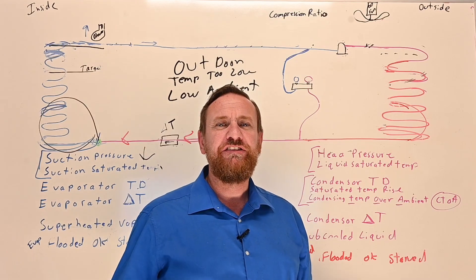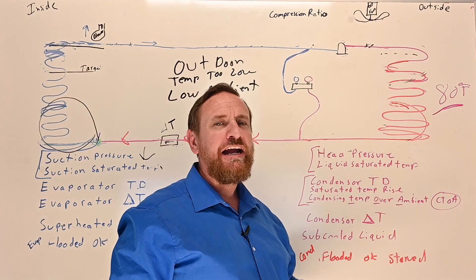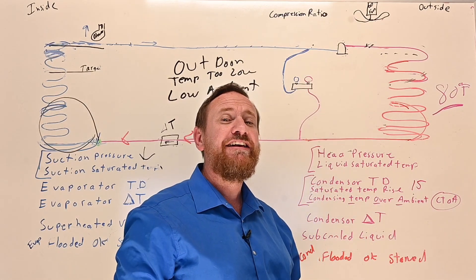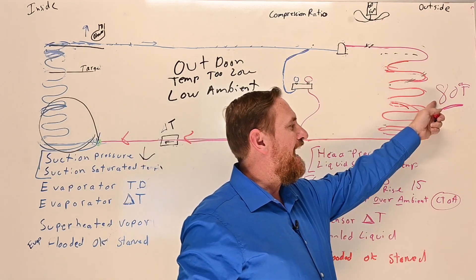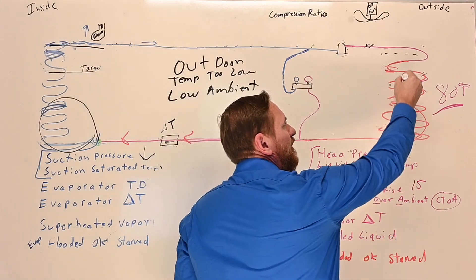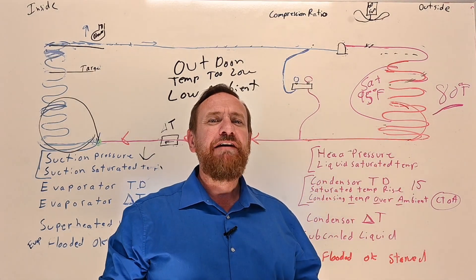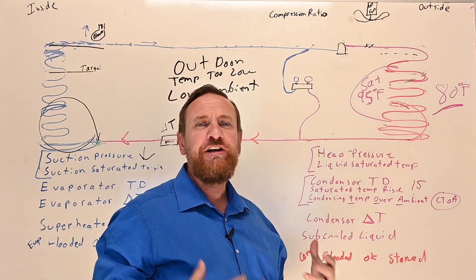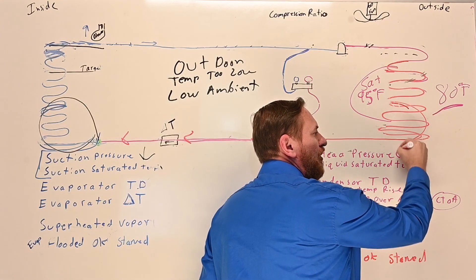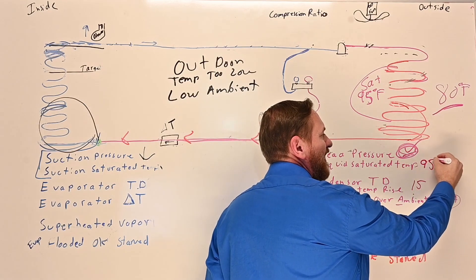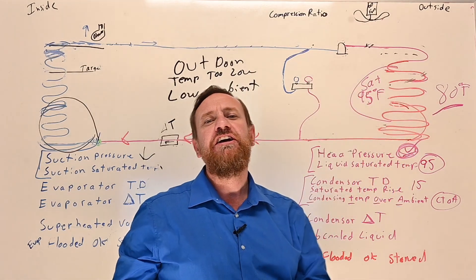So here's an example. We're going to pick 80 degrees. It's a good safe number. So if we say our outdoor temperature is 80 degrees Fahrenheit and we think about it being a typical high efficiency system, let's think about our temperature difference being approximately 15 degrees for some of the newer units. And remember, as those units get older, the larger that TD is going to be. But let's just say we have a 15 degree TD between the refrigerant and the air. So if I take 80 and I add 15, that comes out to be 95. So I want my saturated temperature to be 95 degrees Fahrenheit. So now that we have a target, we know what we're looking for. Now what we can do is use our temperature pressure chart. And if I use my temperature pressure chart, I find what refrigerant I'm working with and convert 95 into a pressure. And whatever pressure that converts to, that's going to be my target pressure I'm looking for.